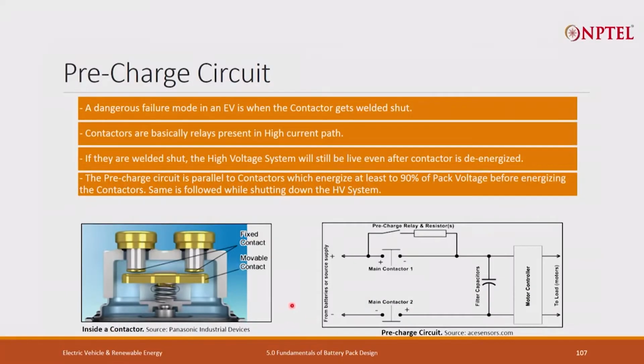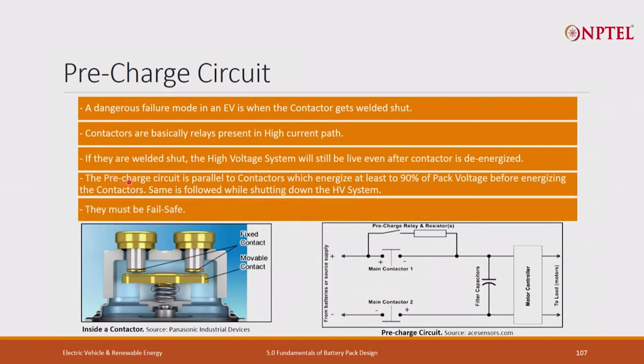So how does it work? You have a main contactor, this is the main path, and then you have a pre-charge relay. So this would be disconnected, this would be connected, so that the potential difference across this path becomes minimum, and then this gets connected so that only the required amount of current flows through the path. The pre-charge circuit is parallel to the contactors. In contactors, we are using external relays or contactors; in the case of semiconductor switching, MOSFETs. This gets energized to at least 90% of the pack voltage before the contactors are energized, so that a huge inrush current does not flow.